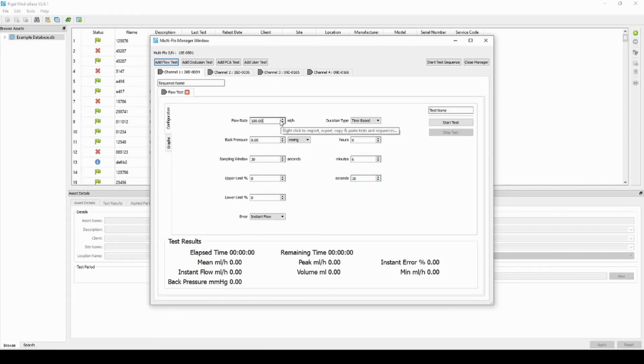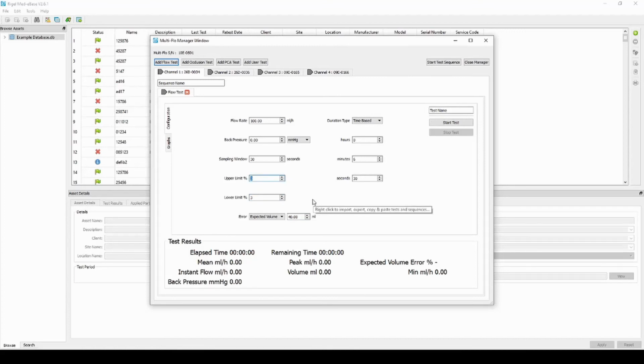We can set the flow rate, or we can select the limits. So we've got multiple parameters within Med-eBase where you can change these, and it's obviously clearly a lot easier than trying to do it on screen with the encoder. Okay, so we'll set the similar limits. Set the flow rate to 400 ml per hour. Expected volume 40 ml.